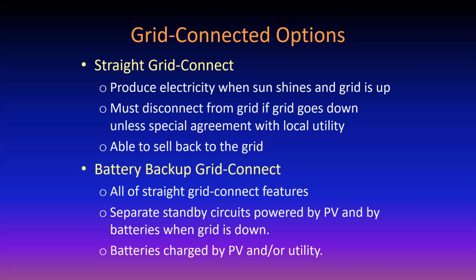Okay, and then there's the battery backup grid connect, and it has all the features of the straight grid connect system, but it also has separate standby circuits that are powered by photovoltaics and by batteries when the grid is down. And the batteries can be charged either by the utility or by the photovoltaic system. If the grid is down, then you depend on the sun to charge the batteries. We are going to focus mostly on straight grid connect. Battery backup systems are basically a 2-hour webinar in themselves, which is also available through PDH. So if you decide you really love this stuff by the time we're done today, I'm not sure when the battery backup comes up again, but it's one that we developed at the request of people who took the straight grid connect. And there's a lot to battery backup, including now incorporating the Tesla Powerwall and so forth as the battery backup system. So it takes a whole 2 hours just to do battery backup.